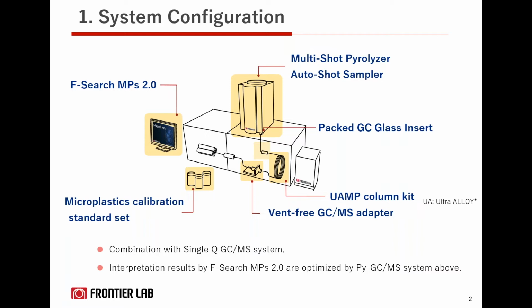So as you could see here, the system consists of a GCMS system. And the heart of the system is the multi-shot pyrolyzer that is called EGA/PY-3030D, which is our patented vertical microfurnace pyrolyzer based on a ceramic furnace. The sample is heated into the furnace to form gaseous pyrolysates, and then they're all introduced into your GC column directly and continuously. So as you learned, this is a single-step flash pyrolysis, that is, everything is directly and continuously getting transferred on your GC column. There is no transfer line. You can also see the AutoShot sampler that is on top of the pyrolyzer, and this accessory can automate a continuous series of analysis up to 48 samples.